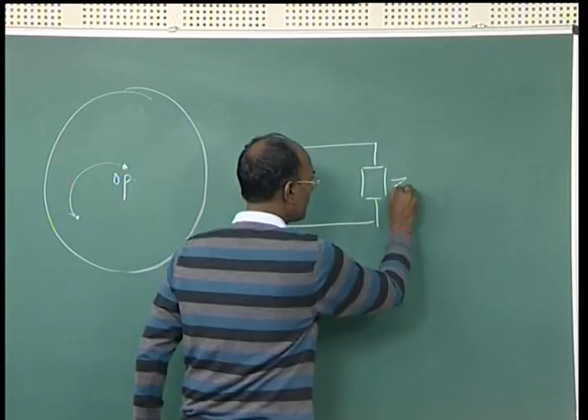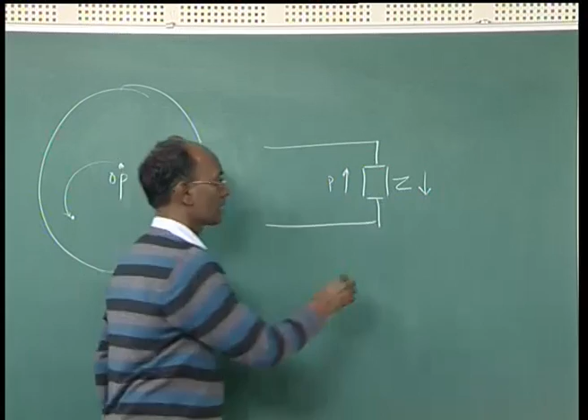For example, consider an impedance Z. If Z is reducing, the power drawn, P, will increase - or equivalently, if the admittance is increasing, power increases. But if this is not happening - if your impedance is decreasing and your power is not increasing - then it is called voltage instability. So in a stable case, both power and impedance are controllable relative to each other.